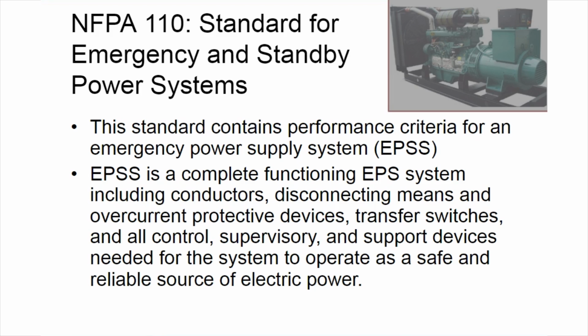So let's take a quick look at NFPA 110, Standard for Emergency and Standby Power Systems. This standard contains the performance criteria for an emergency power supply system, and it defines a system as a complete functioning EPS system, including conductors, disconnect means, overcurrent protection devices, transfer switches, and all control supervisory and support devices needed for the system to operate as a safe and reliable source of electrical power. Additionally, there's three major criteria that define an EPSS in NFPA 110, and those are level, class, and type.